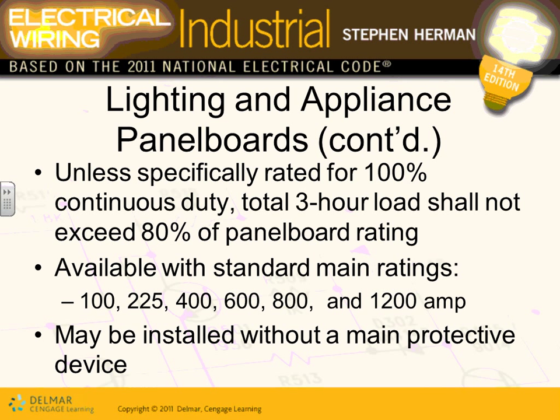These are the sizes of the panel. When it comes to the size of the panel, guys, there are two sizes: the size of the copper or aluminum inside the panel, and also the size of the circuit breaker ahead of it. So when I say I have a 100 amp panel, in reality, for three phase, you don't have a 100 amp panel. What they do is they have a 125 amp panel, but they put just a 100 amp circuit breaker ahead of it. Everybody understand that the size of the panel could be slightly higher than the size of the circuit breaker? So you're looking at the sizes of the panels here or the circuit breaker that can be on them.